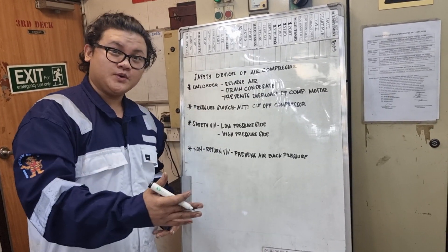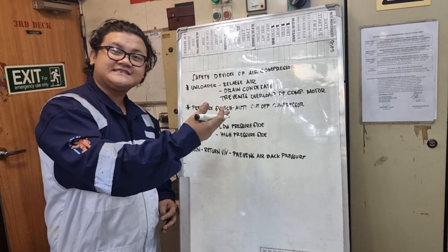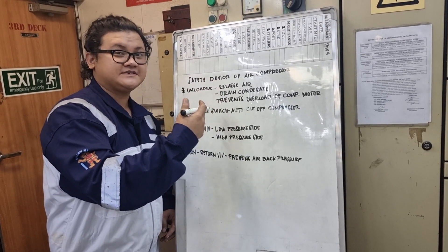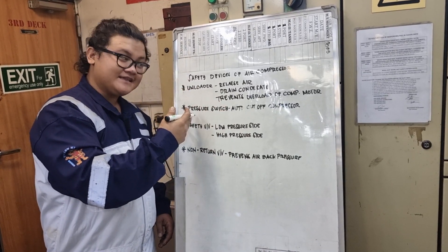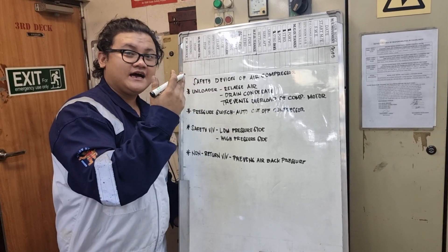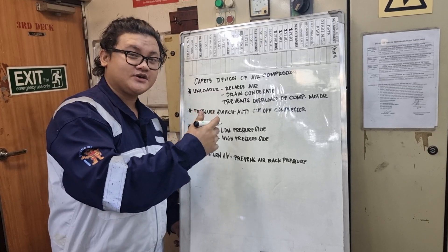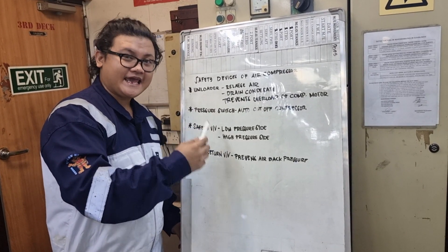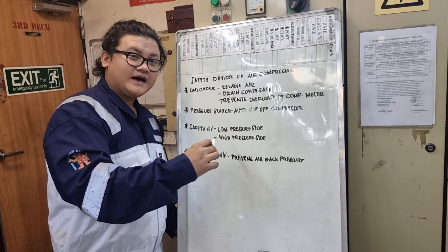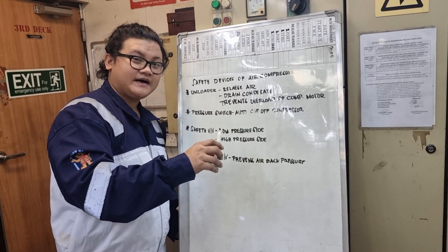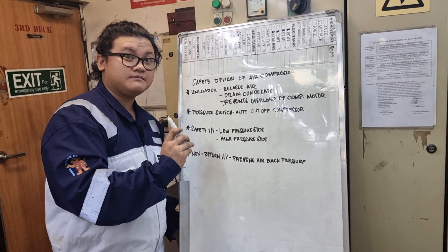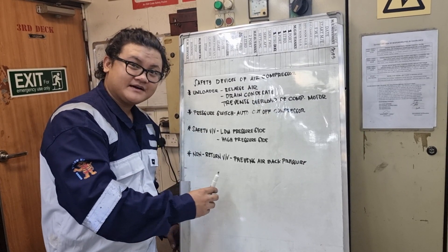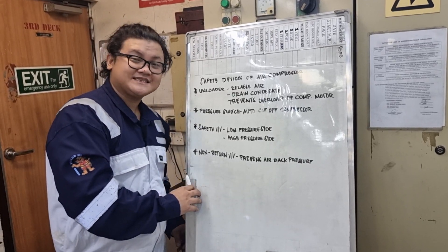Again, let's review. Four types of safety devices of air compressor: Unloader releases the trapped air in the compressor that prevents it from starting, and also drains water. Second, pressure switch automatically cuts off or turns off the compressor once you attain the desired pressure set in the pressure switch. Safety valve releases air once the setting of the safety valve is attained, also to prevent your compressor from being damaged. And non-return valve prevents air back pressure coming back to your compressor, which is attached to the discharge side.